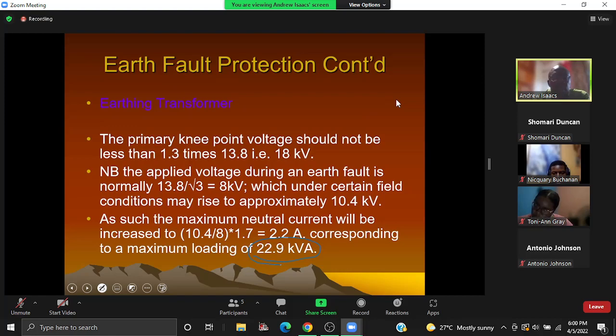Because remember all of this. Remember I said that this 10.4 is on the primary. Right? We had the 1.7, which was for the resistive part, and the 1.7 for the leakage capacitance. So we are saying that the current would also increase by that factor. So the kVA load would now be the 2.2 times the 10.4. So this would be the loading on the transformer.